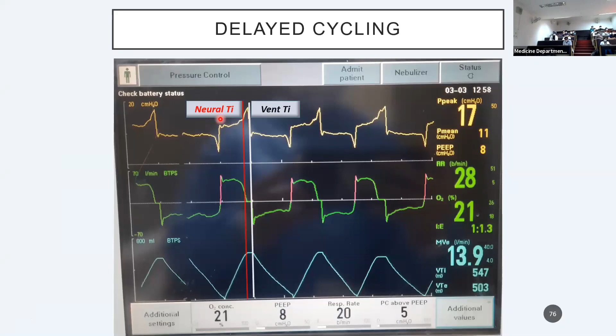There's dynamic hyperinflation. So management in PCV mode, of course, you decrease the inspiratory time. You may also decrease the rise time. Rise time is the time it takes from pressure to reach the peak in pressure control. So if you decrease the rise time, the inspiration may occur earlier.